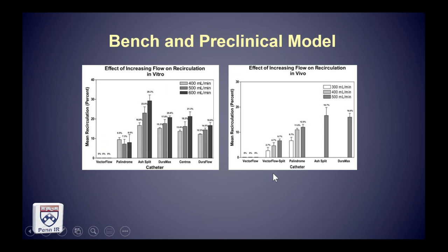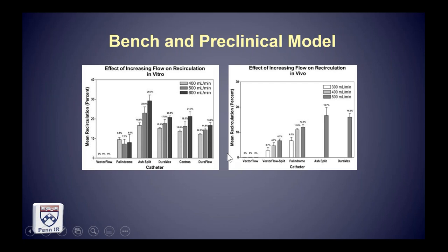From there we went to a bench and preclinical model to validate what was shown in CFD testing. In terms of recirculation — where less is more favorable — at flow rates vastly exceeding what would be used for clinical hemodialysis, the vector flow catheter outperformed all other catheters on the market. Similarly, in an animal model, recirculation was basically absent at all flow rates achieved.